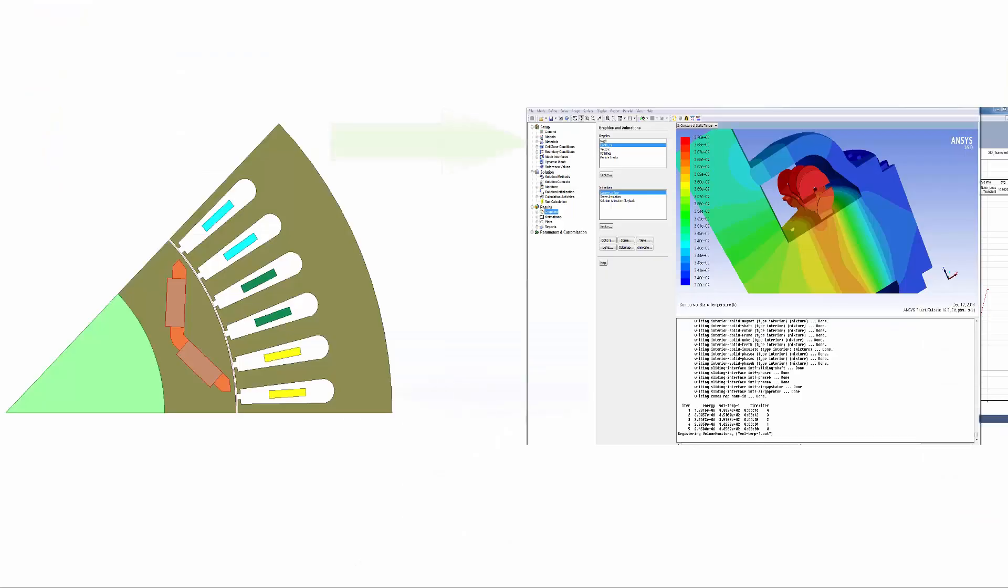You have seen the process to couple ANSYS Maxwell to ANSYS Fluent for a combined electrical and CFD thermal analysis. The temperature profile evaluated from Fluent changes the BH characteristics of the interior permanent magnet motor based on the thermal coefficients defined in Maxwell. The main advantage of using CFD simulation is that the heat transfer coefficients are automatically calculated and updated based on fluid dynamics solution. This method provides a more accurate solution for rotating machine design.